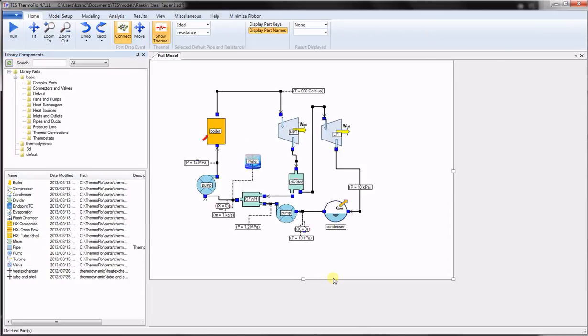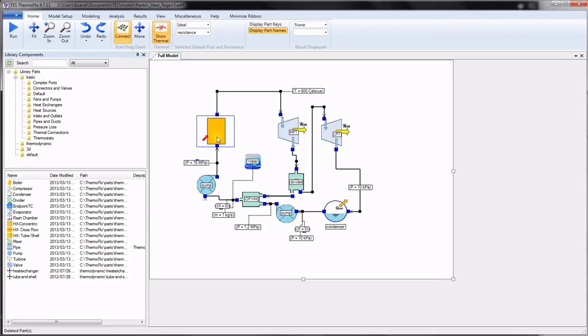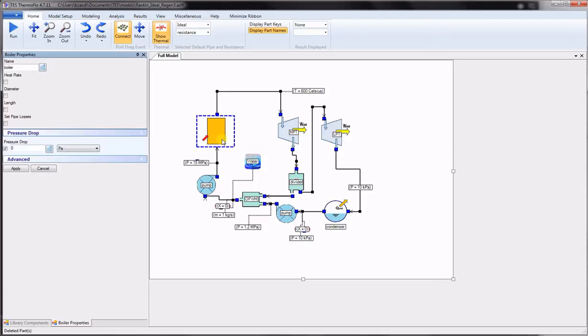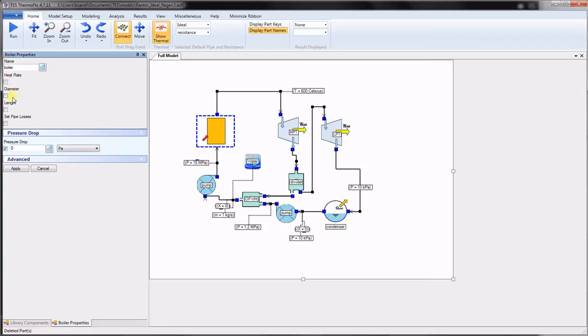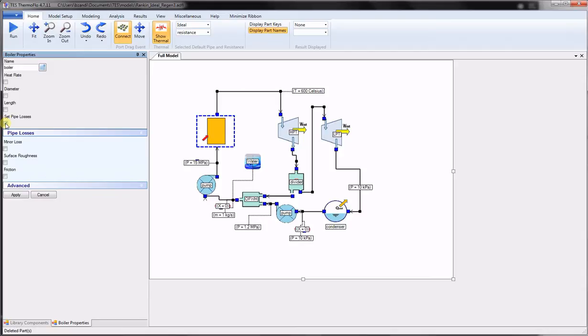Another group of components are the single path heat transfer devices which includes condensers, evaporators, boilers, and in general any heating chamber. The primary variable here is the heat rate which the user can set as positive to indicate heat in or negative for heat out of the device. Or alternatively, it will be solved for. The user can also account for the pressure losses in the system by either entering a value for the pressure drop or set the switch for set pipe losses to enter values for the minor and friction losses.